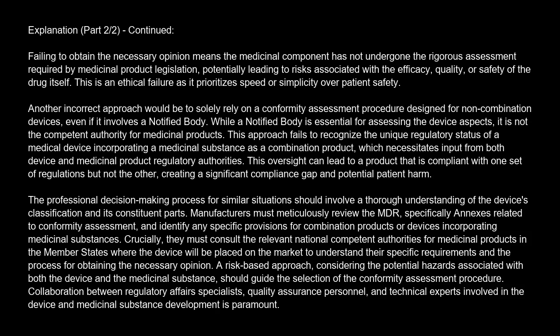This approach fails to recognize the unique regulatory status of a medical device incorporating a medicinal substance as a combination product, which necessitates input from both device and medicinal product regulatory authorities. This oversight can lead to a product that is compliant with one set of regulations, but not the other, creating a significant compliance gap and potential patient harm.